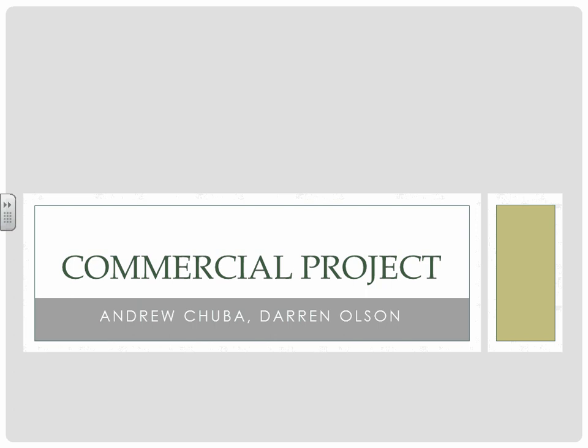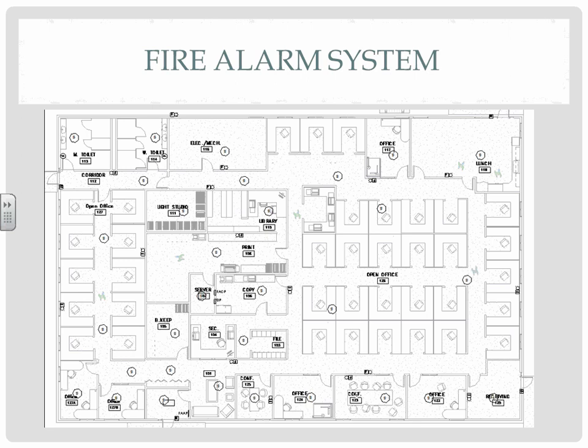All right, I'm Andrew. I'm Darren. This is a fire alarm system we did in the building. You can see there's a smoke detector in the open office every 30 feet, and in every room there's a smoke detector as well. Right here is the control panel, and the annunciator panel is down by the door. At each door there's a manual pull station. And instead of the horn in the bathroom, we just did visual, because of the echo that would be in there.